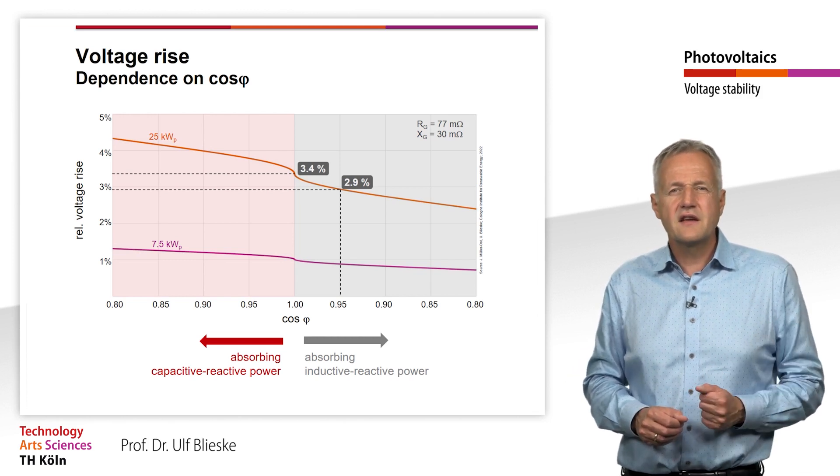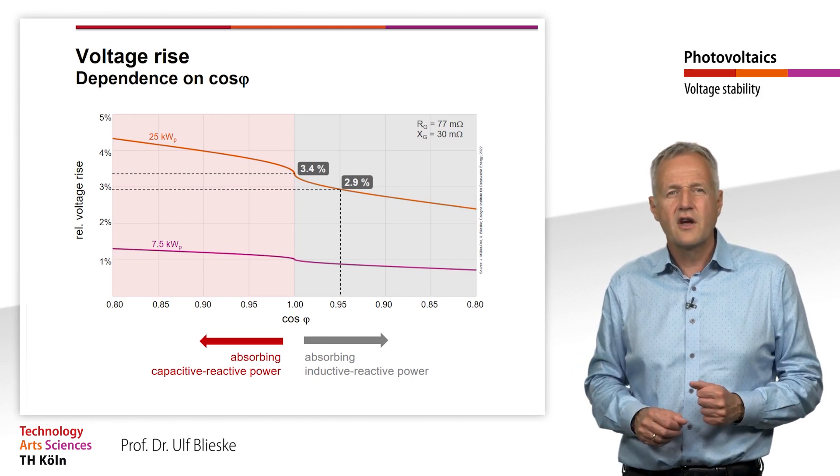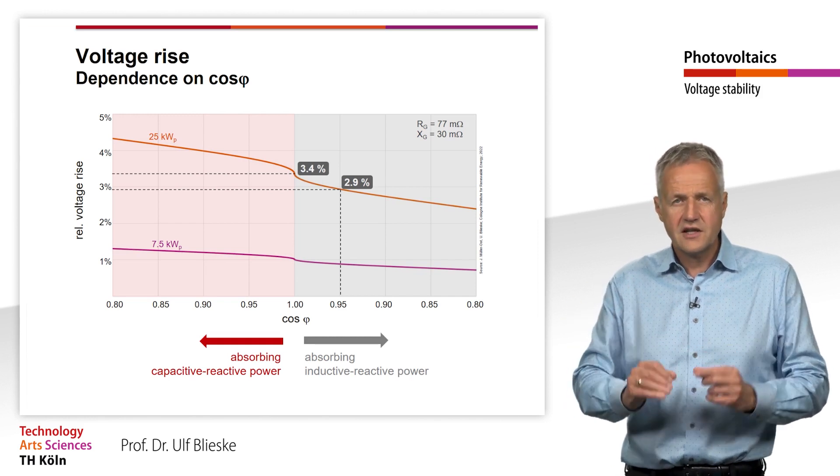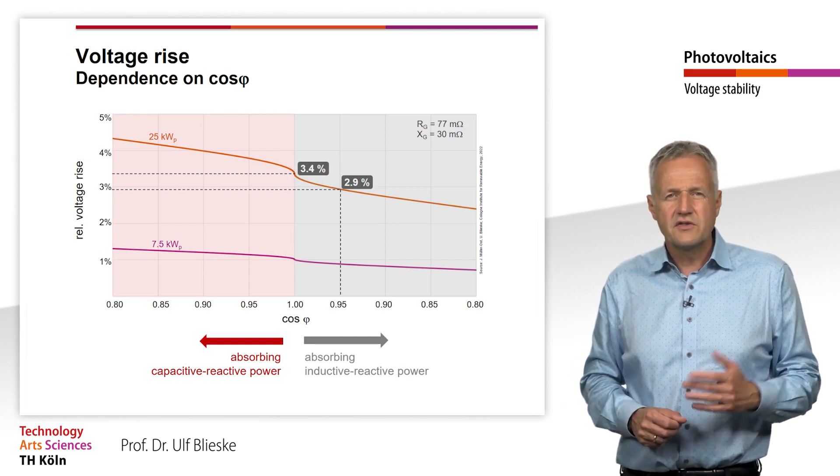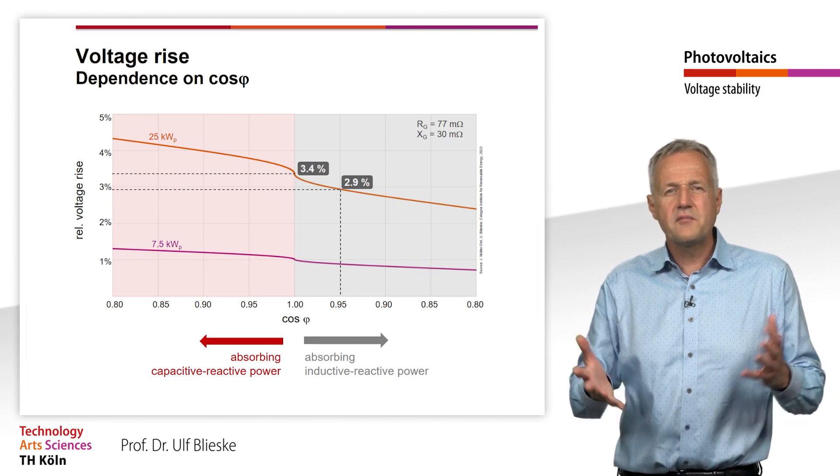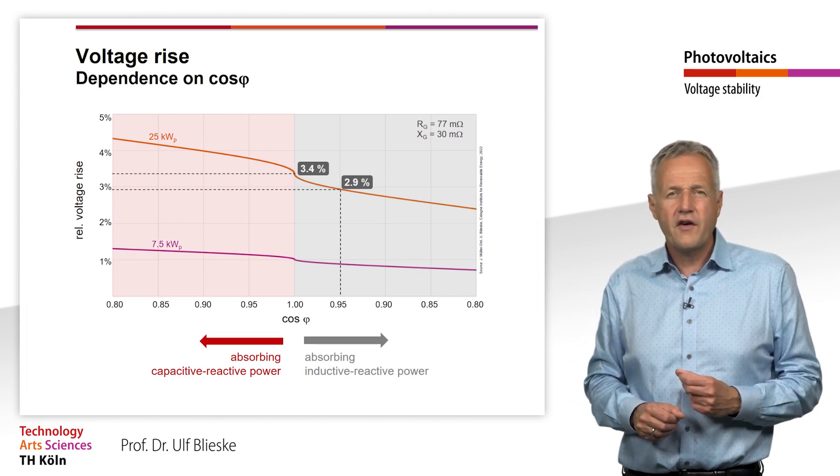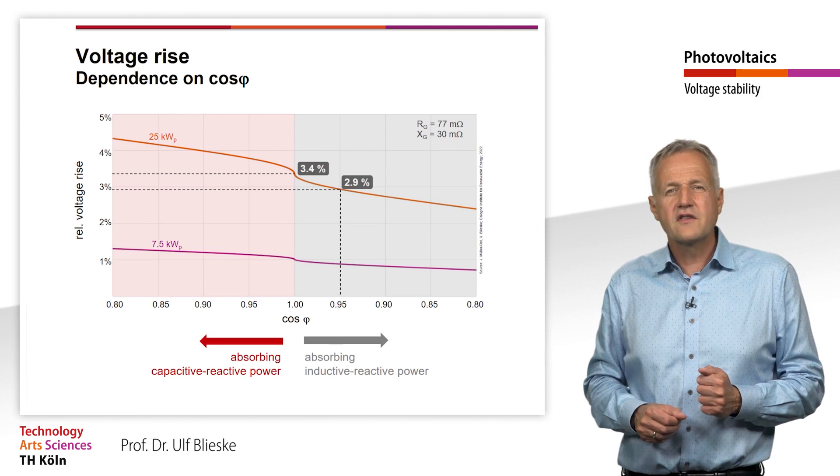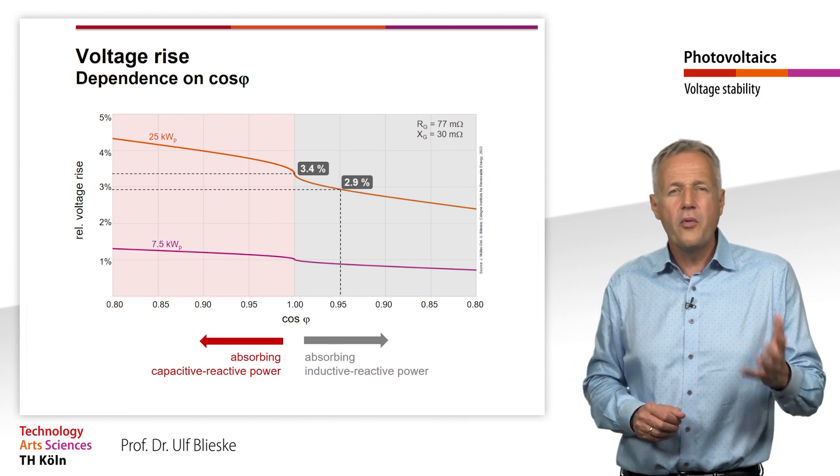If we now set an inductive phase shift on the inverter, the voltage rise drops significantly. With the larger PV system, it can be reduced by 0.5 percentage points with a power factor of 0.95.